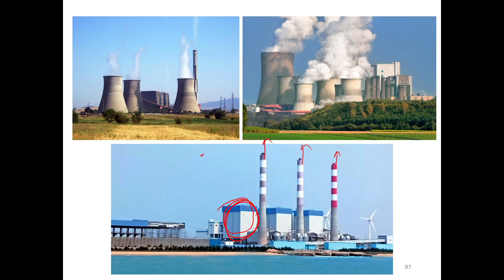Then the next picture, I want you to identify this picture. This is actually the only coal power plant in Sri Lanka. This is a picture of the Norochcholai power plant. You can see the exhaust stacks, 1, 2, 3. That means we have 3 boilers. What you see in this building is the boiler, all of this building is boiler. You have one boiler, another boiler here. The boiler produces steam, and steam from this boiler goes to the turbine. One of these turbines produces 300 megawatts of power, and altogether, 3 times 3, we basically produce 900 megawatts from the Norochcholai power plant.